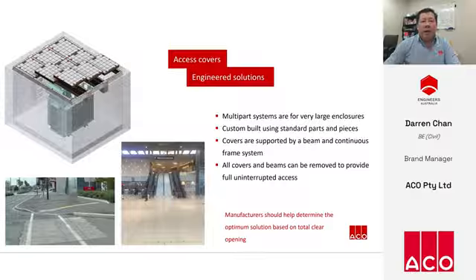Multi-part access covers are a collection of single-part covers assembled together and supported by beams to span large enclosures. The beams and covers are all removable, so you can still access an enclosure without obstruction. AS3996 only governs single-part covers, not multi-parts, so each cover needs to be load rated to AS3996, not the assembly. The beam therefore needs to be structurally designed, and manufacturers should recommend the beam size and bespoke system based on the total clear opening of the underlying enclosure.